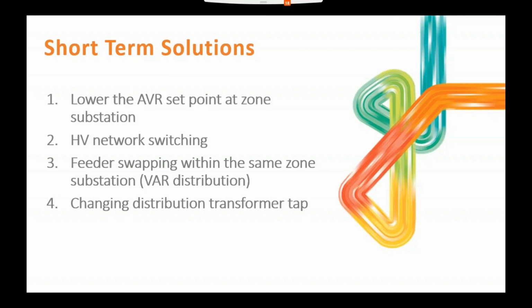We were able to do some HV network switching and feeder swaps on the same zones. You might have one feeder that's got a lot of reactive reverse power, and if you change some open points and do some switching, you can fix that and hold the voltage up for a short period of time.